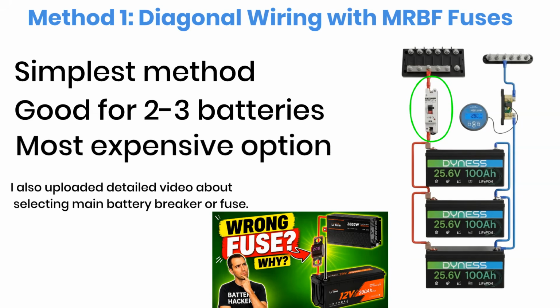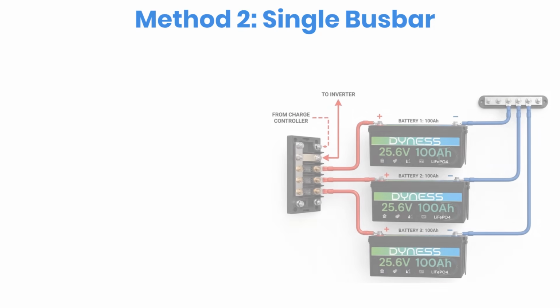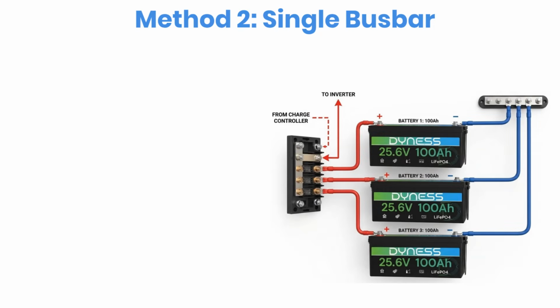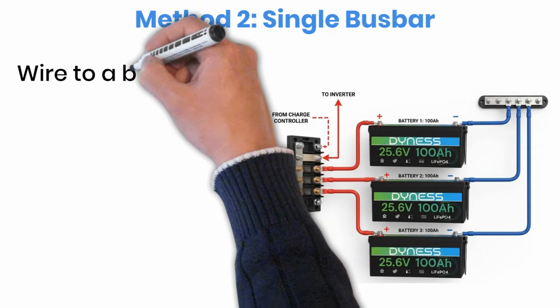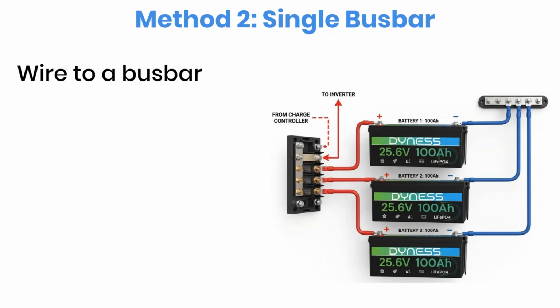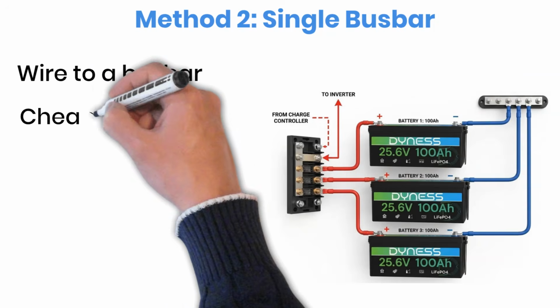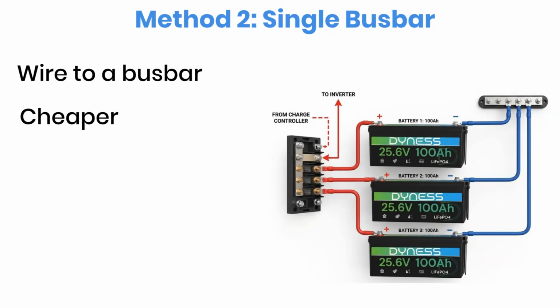Now let's move on to the second method. Instead of using separate cables all the way to the main bus bars, each battery connects to a single mega-fuse bus bar. Your inverter, charge controller, and the batteries all connect to this same fused bus bar. One of the biggest advantages of this design is cost. Because each battery branch only carries the current from that individual battery, you can often use smaller cables for those connections. Mega fuses are also usually less expensive than MRBF fuses, making this setup much more budget-friendly.